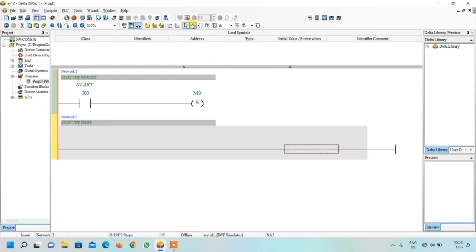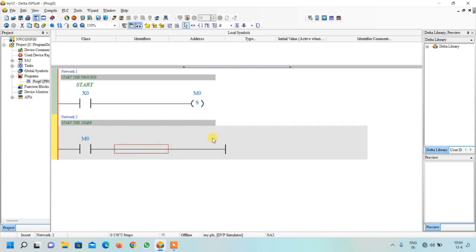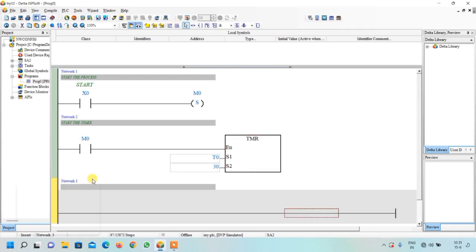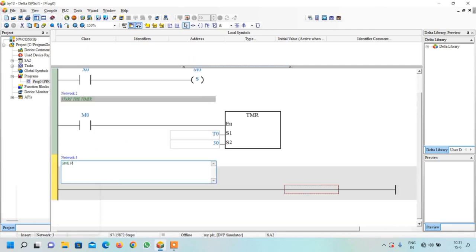Insert a new network. If the process is on, we want to start the timer, so select contact, give address M0, and press Enter. If the process is on, the timer should start and run up to the preset value. Go to Functions Block, select All Types, type TMR — the mnemonic for timer — and click Insert. Write timer number T0 and preset value 30, which means 3 seconds. Insert another network and write a comment: 'to counter'.